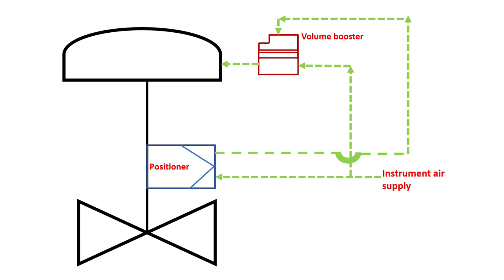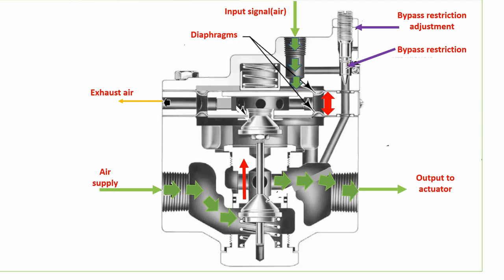This is the position of a volume booster in a control valve. You can see that the volume booster is located immediately on the actuator side — the volume booster output goes directly into the actuator. It is the final component of your control valve or shutdown valve assembly. The input air signal comes in from the top port.